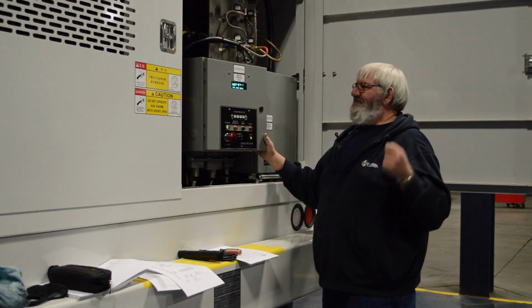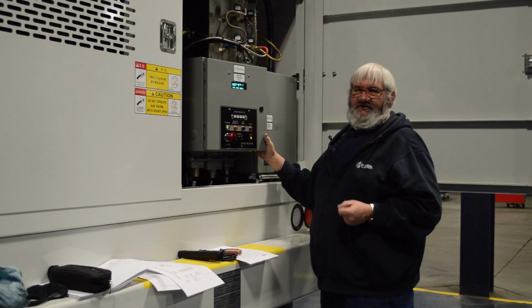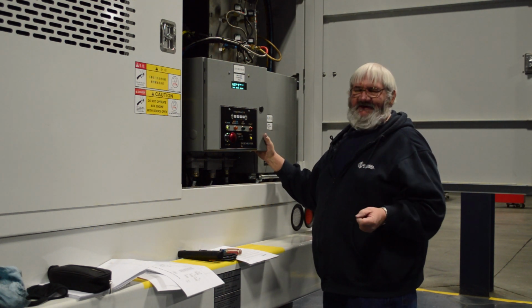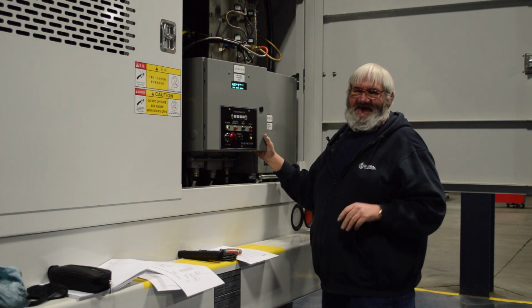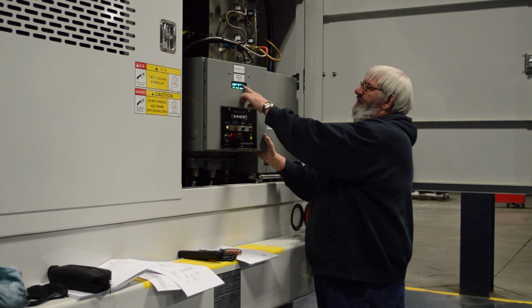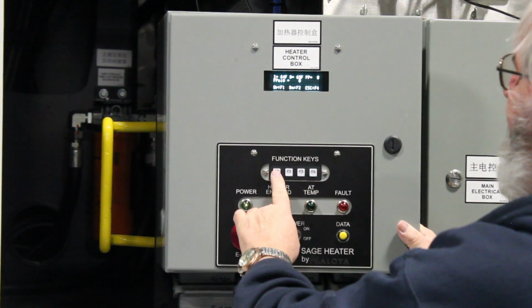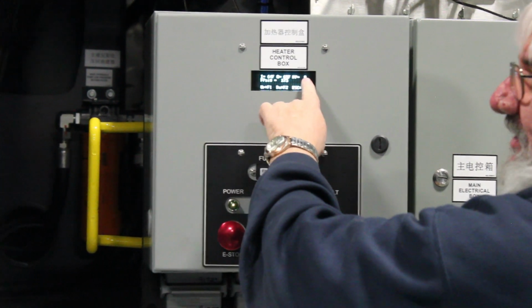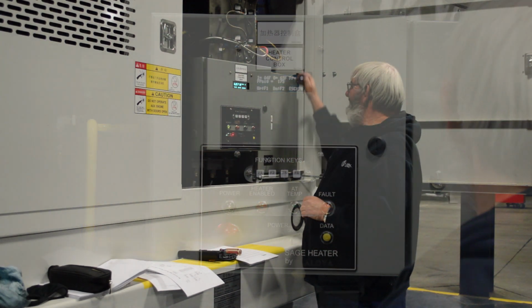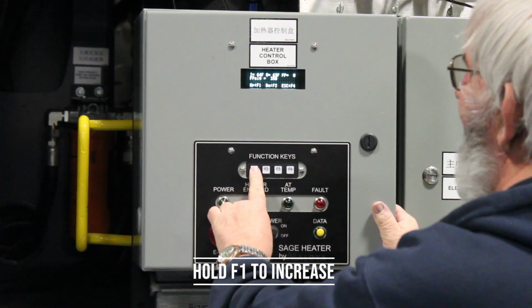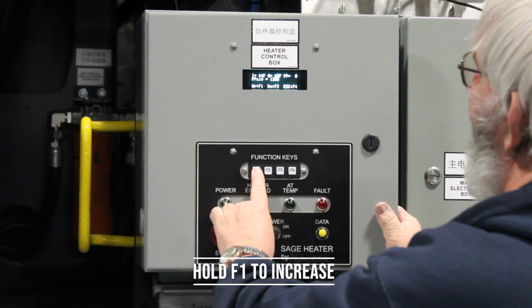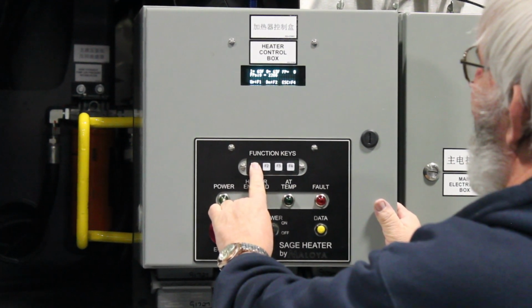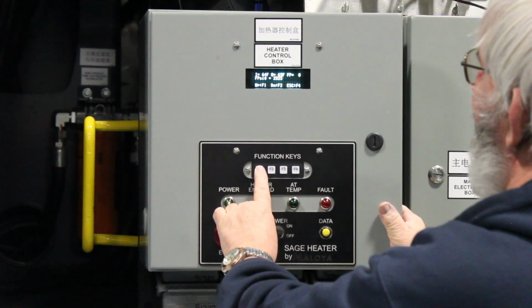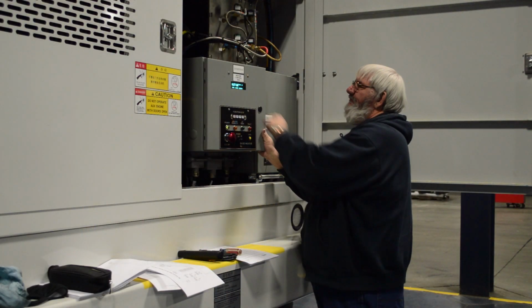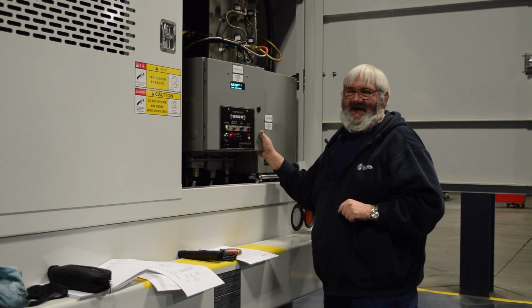Now remember, as you increase your signal, your fuel pressure should come up. Now at zero signal, you should be around 50 to 75 psi. And this would be recorded right here. So as you increase your signal, your fuel pressure would go up. You would see this on the manual gauge in the fuel manifold. As you get all the way up to 2650, your fuel pressure should be around 300 psi.